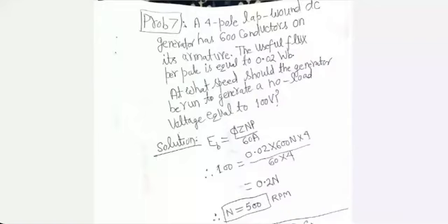1500 RPM is not easy to obtain unless you use gas turbines. Hydro turbines do not give very high RPMs, 200, 300, 400, 500, etc. Wind turbines give even lower values of RPMs. Diesel generators give much better.